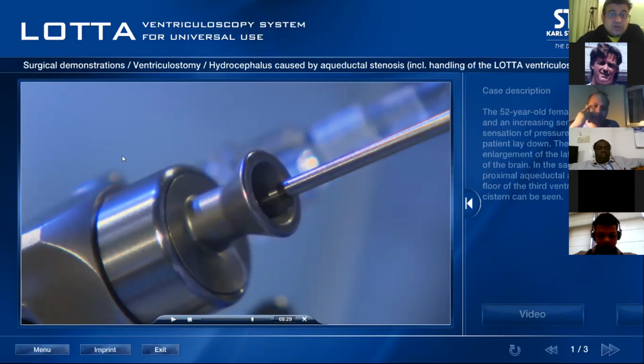You are seeing in 2D and you are working in 3 dimension. So we have now put a black marking. So watch out for this black marking. The moment it reaches the tip of the circumference of this funnel, that means your instrument is exactly at the tip of the neuroendoscopic sheath, and further advancement of the instrument will take your instrument out.